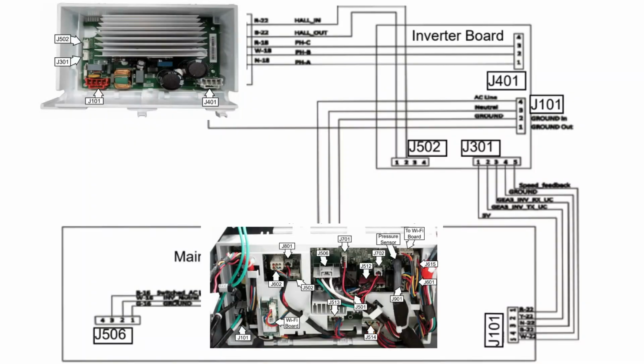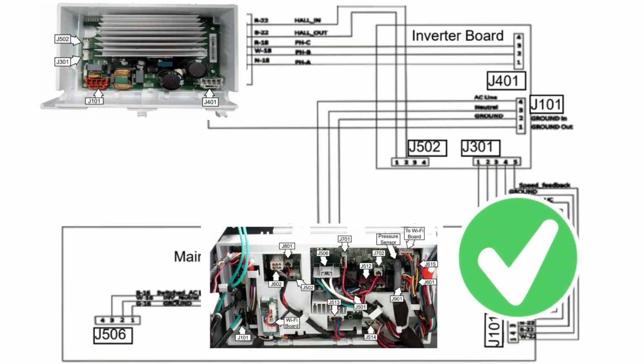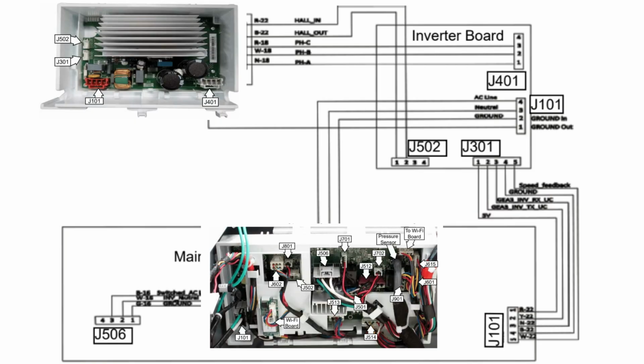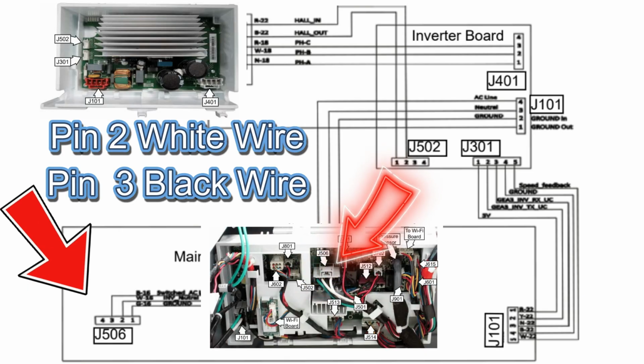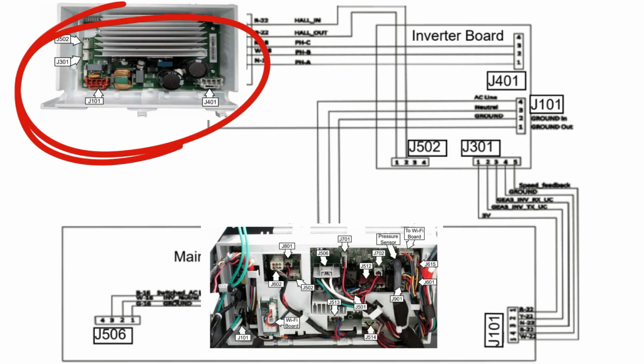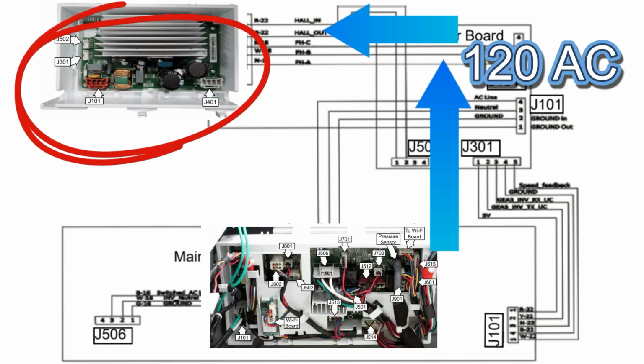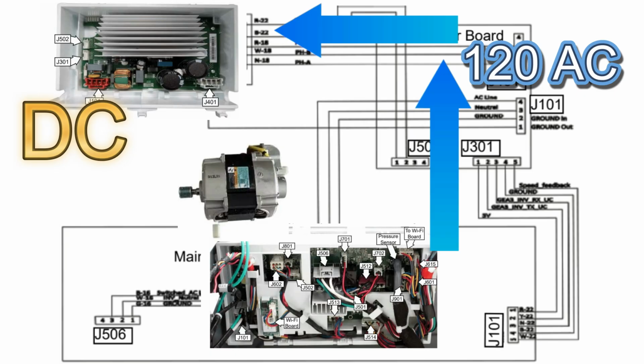The inverter receives 120 volts from the main control board. If you're getting 120 volts from the main board, then your main board is good. You can check this at connector J506, pin 2, which is the white wire, and pin 3, which is the black wire. The inverter converts that 120 volts AC into a variable DC voltage that powers the motor.